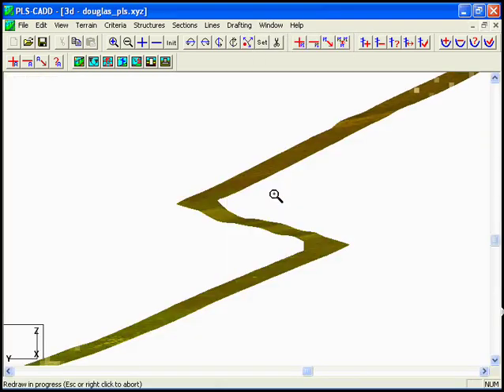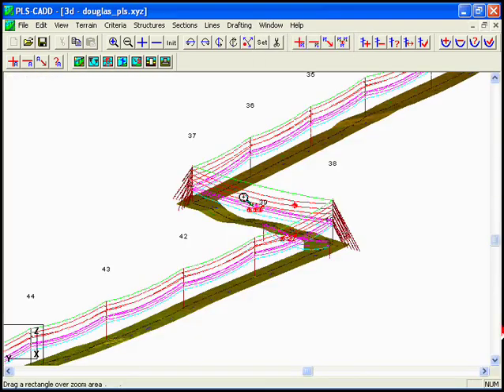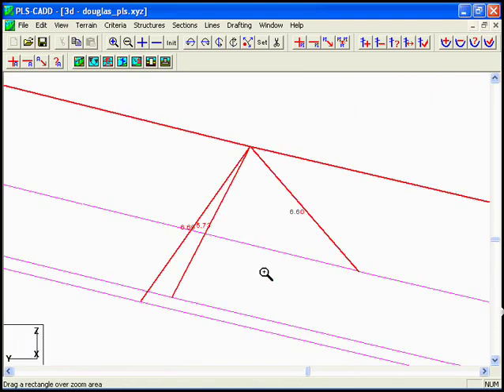So we'll close out that report and graphically look at that again. We can see we have a couple of them here. Looking out here in mid-span between 37 and 38, you can see that's where the clearance problems are. So we have our 5.73 from our lower phase to the inside of our distribution, 6.65.